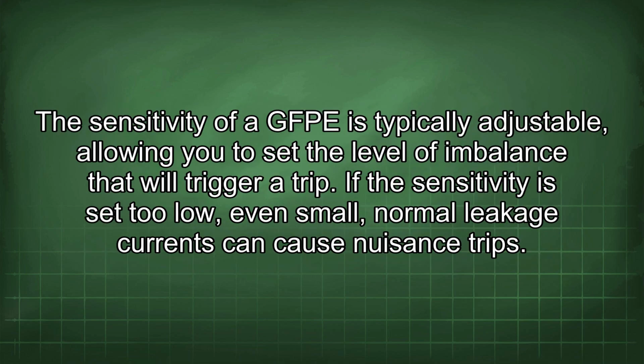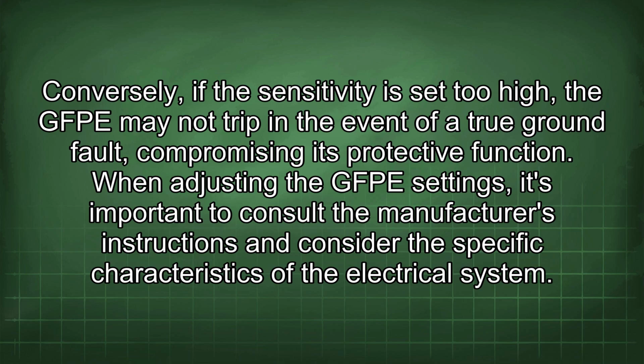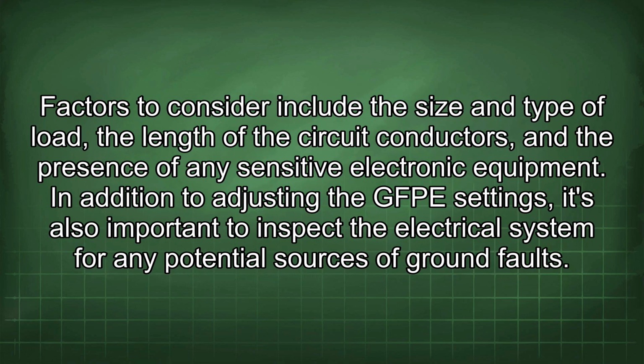The sensitivity of a GFPE is typically adjustable, allowing you to set the level of imbalance that will trigger a trip. If the sensitivity is set too low, even small, normal leakage currents can cause nuisance trips. Conversely, if the sensitivity is set too high, the GFPE may not trip in the event of a true ground fault, compromising its protective function. When adjusting the GFPE settings, it's important to consult the manufacturer's instructions and consider the specific characteristics of the electrical system. Factors to consider include the size and type of load, the length of the circuit conductors, and the presence of any sensitive electronic equipment.